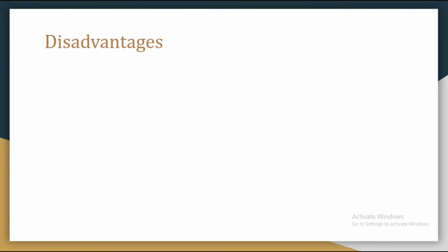Now we will look into the disadvantages. It is non-linear. The linearity of a thermocouple is lower than that of an RTD, right? Sensitivity is low. The sensitivity of a thermocouple is lower than that of a thermistor.